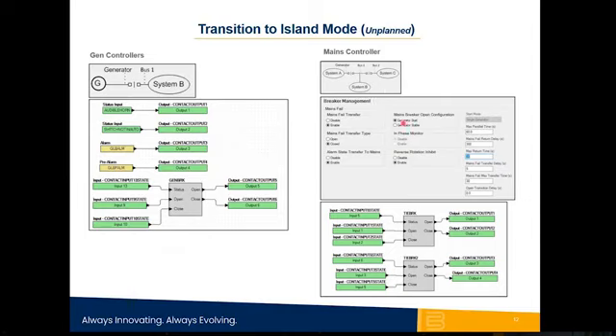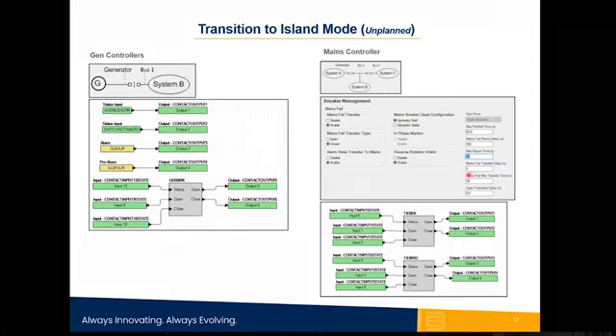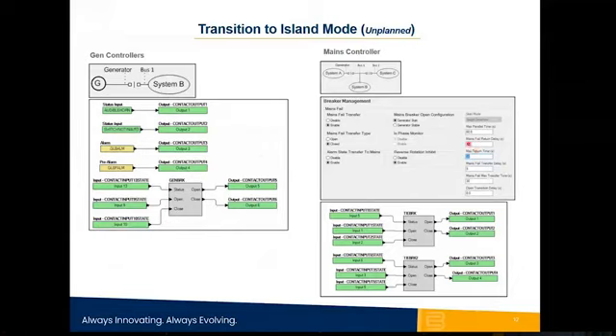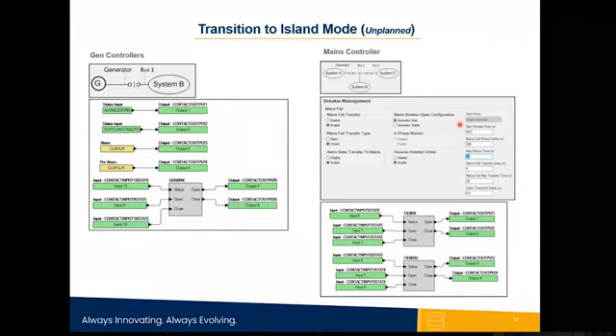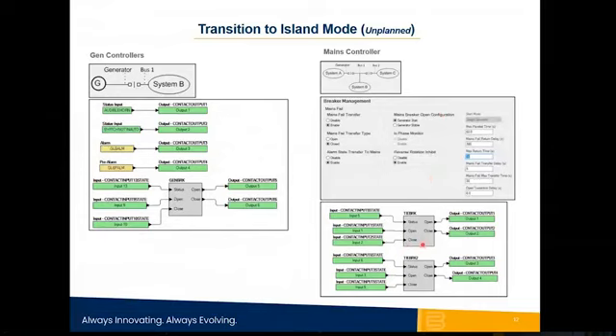The settings here are all your timers. So the delay time and your return delay time give the utility sufficient time to become stable. All these settings are listed right here. And all these functions are canned in the firmware. So just by implementing a few settings, you can achieve an entire transfer scheme using a 2020 HD. And then there needs to be some logic for the two breakers. So we showed that the 2020 HD at the mains is also controlling the group 2020 HD downstream.